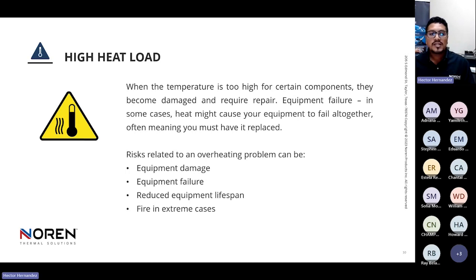High heat load. This is another problem for electrical panels. Always remember that when you are adding electrical equipment to the electrical panel, you are adding heat, since all this equipment generates heat. Keep in mind that the cooling capacity installed in the electrical panel must be enough to take away this heat. We can cause damage to our equipment from higher temperature. We can cause failure. We are going to reduce the lifespan of our equipment, even fire in extreme cases. We can find some other problems that sometimes are related or not to overheating.